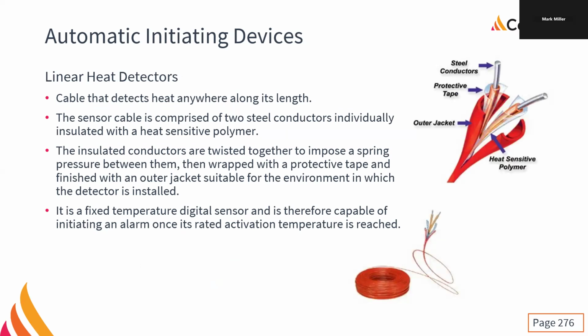Moving on from our two types of smoke detectors, let's go back into the world of heat detectors. Linear heat detectors. I've worked with this stuff a couple times. It's pretty cool. You've got to be really careful of it. It comes in a 100-meter roll or whatever it is, and you can use the entire thing in one shot. And it is a cable that can detect heat anywhere along its length. So if you have a 100-meter run of this stuff, that's a 100-meter long heat detector. It is really cool stuff.